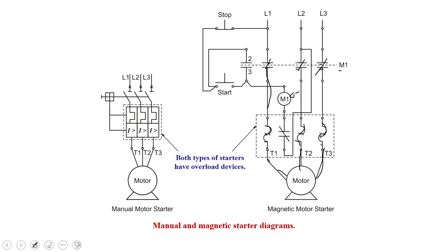Now on this one, we also require a control circuit of some kind. So we go through our stop-start station, and when M1 is energized, holding contacts 2 and 3 close, and it will seal that holding in. So it'll keep going until we press the stop button. In the event of an overload, the overload contact would open and it would de-energize the coil, and our power contacts would open back up.